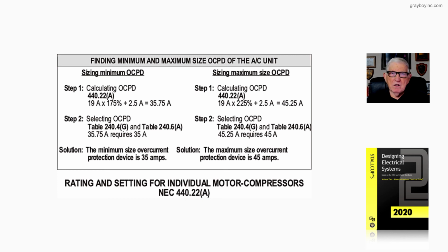Now in this particular drawing, an illustration, we're simply sizing the rating and setting for an individual motor compressor in accordance with 440.22(A). In a later illustration, we will size the conductors.